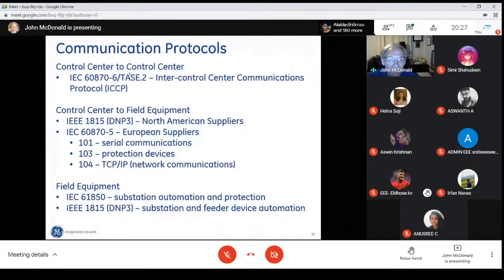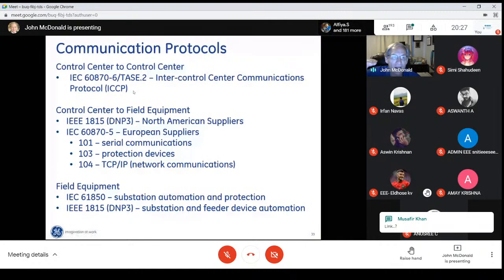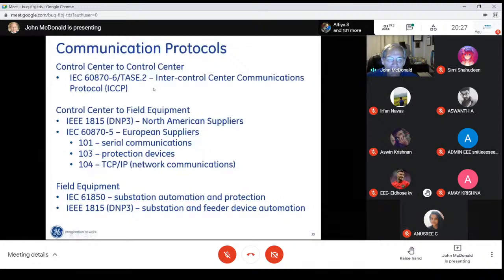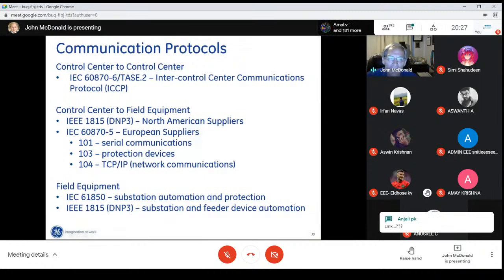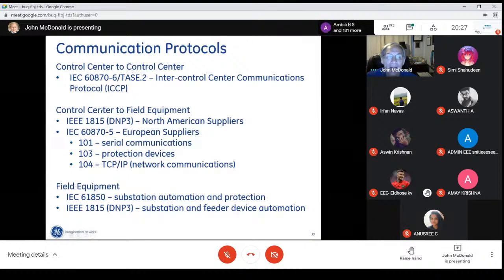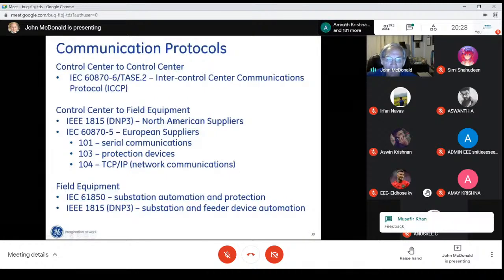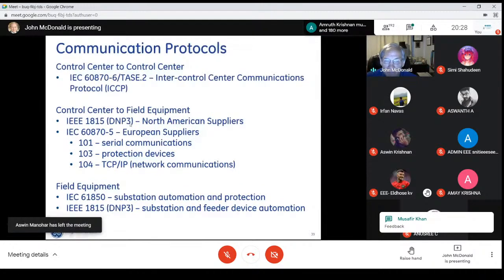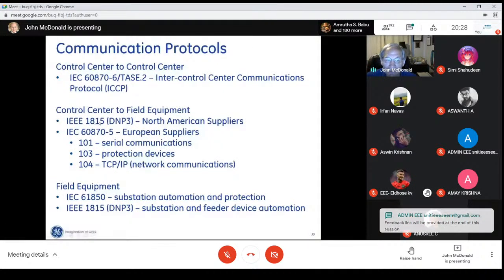What makes it easier too is, let's look at 3 levels of the electric grid, 3 hierarchical levels. Control center to control center, there's one worldwide standard - we call that Inter-Control Center Communications Protocol, or ICCP, for one utility to communicate with another utility. Second is control center to field equipment. There's really 2 standards in the world that are used: one is with North America suppliers, called DNP3, Distributed Network Protocol 3, which is also IEEE Standard 1815.